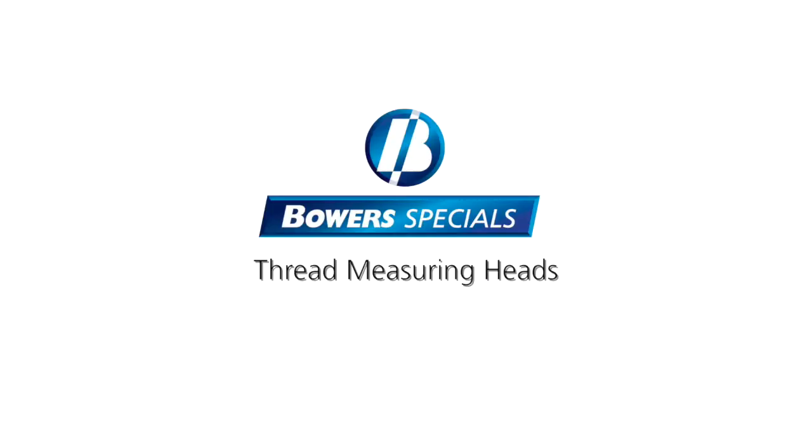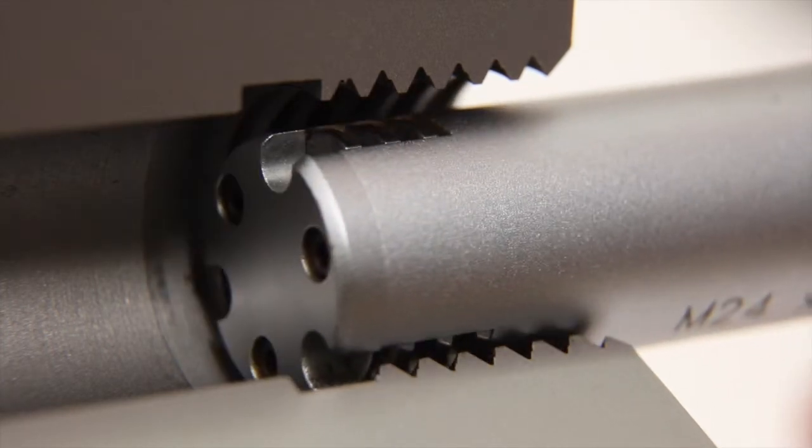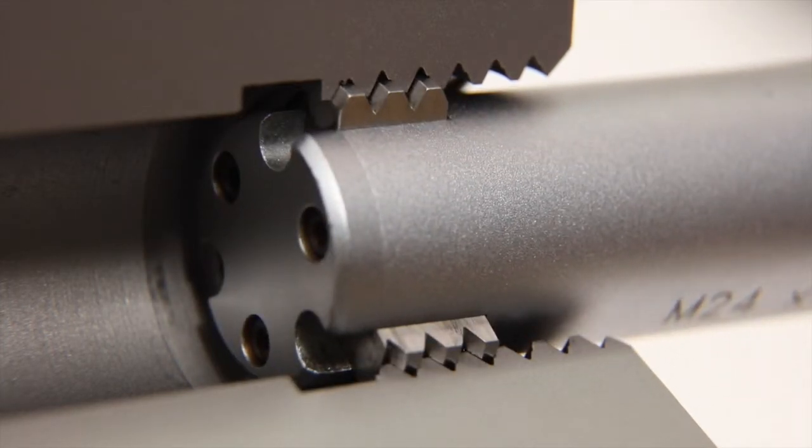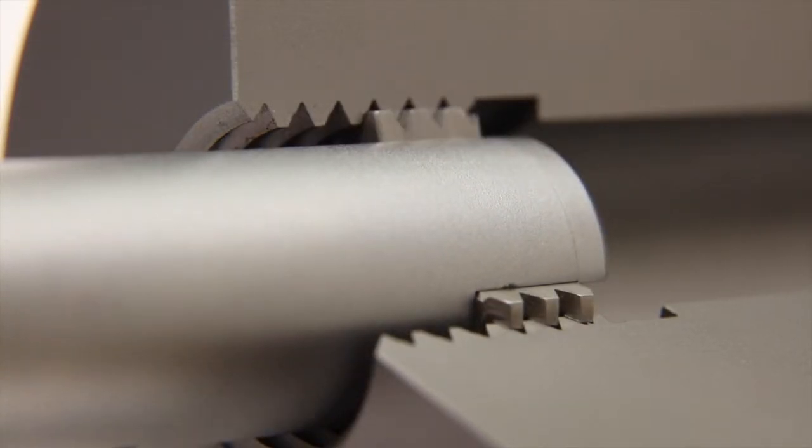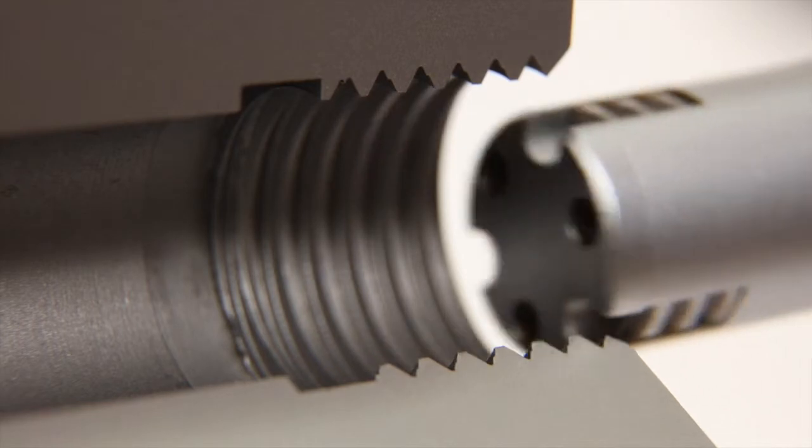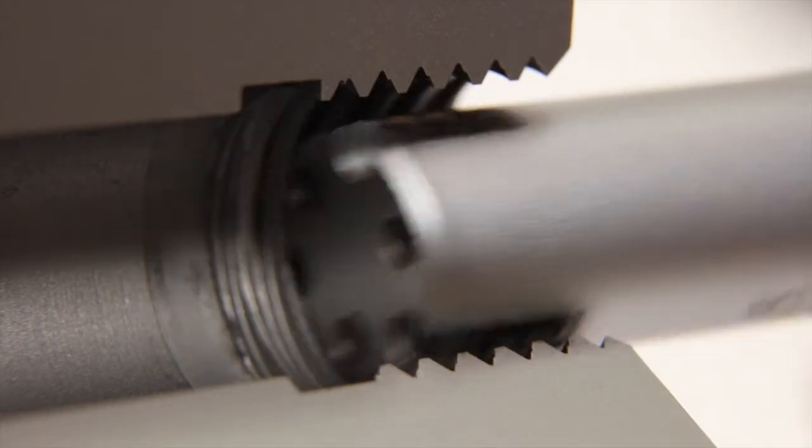Moving on to threads, Bowers thread measurement heads are typically used for the inspection of effective pitch diameter. Heads are also available for the inspection of minor diameter, major diameter and true pitch diameter. The functional pitch diameter head can be identified by its multiple thread form anvils.